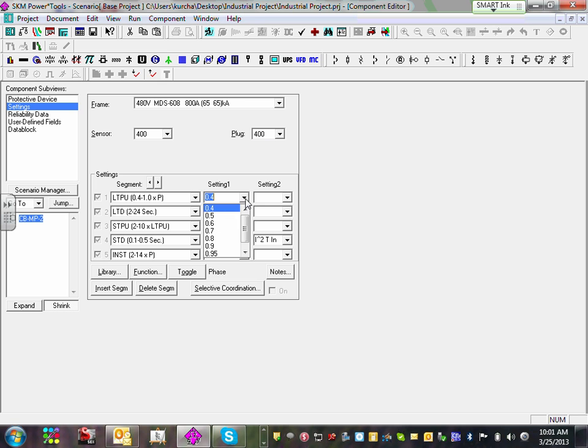Then do me a favor, right here - can you see the long time pickup? Go set this one to 1. Now you've just picked yourself a circuit breaker running at 400 amp. Every load, every circuit breaker you have that's 800 amp or less, you can use this particular circuit breaker - you don't have to go to the library.